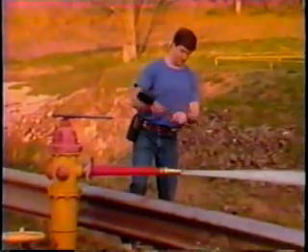The problem in using an underwriter's play pipe, though, is that you don't use the diameter of the hydrant outlet, but rather the diameter of the tip of the play pipe as d in the equation we just showed you.